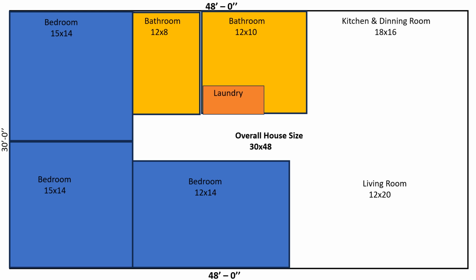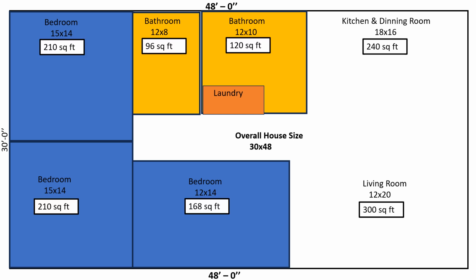So first thing we want to do is get our square footage. If you look at the next screen, this bedroom, 15 by 14, is 210 square feet. Got another bedroom, 210 square feet. The half bath is 96 square feet. The main bathroom is 120 square feet. The third bedroom is 168 square feet. The living room is 300 square feet. And the kitchen dining room area is 240 square feet.